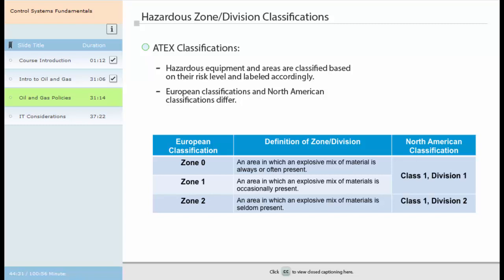In North America, the classifications are consolidated into two divisions. Class 1, Division 1, is an area in which an explosive mix of materials is normally present. Class 1, Division 2, is an area in which an explosive mix of materials is not normally present but may accidentally occur.